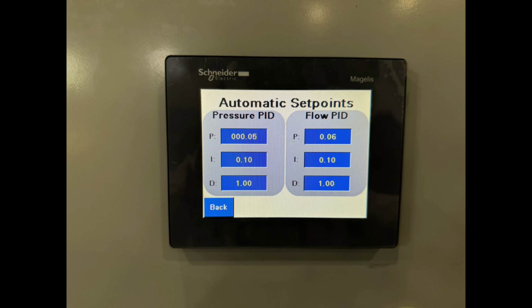If you go back to the menu and you continue on, you can see the PID settings here. So for our pressure PID, we have the P, the I, and the D that you can all change through here. This was not the actual final measurement or the final numbers I used for the PID. I went through and I took photos as it was running, as I was trying to figure it out. This was working at that time, but I did have to change a few things to get it to that perfect curve that we wanted.